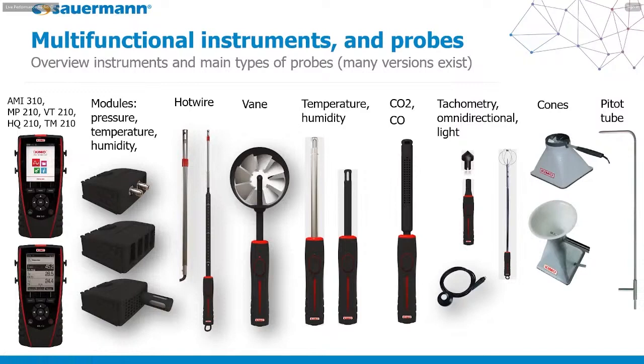So like I mentioned, for pressure, you can plug in these black modules into the back of the instrument. The top one here next to the instrument, that has the two metal ports on the side, allows you to do differential pressure measurement. You can also do humidity with that. I mentioned before we have the hot wire probes, which, at the very tip of those probes, is exactly as it's named. It's actually a hot wire. As the air passes through it, it cools that hot wire. You correlate that to the airflow. And in the example of the second hot wire probe here, you can see the probe extends out. It's a telescopic probe, so you can change different lengths of it based on the diameter of the duct or the pipe that you're inserting it into for the measurements.